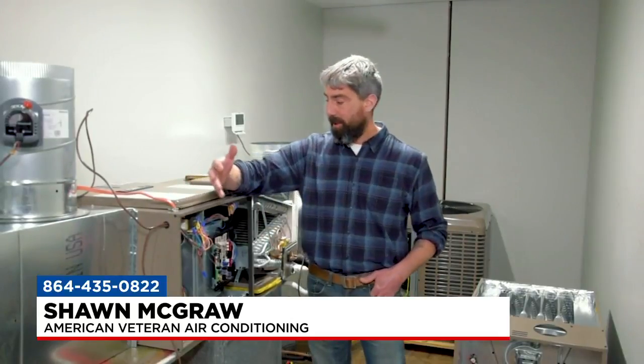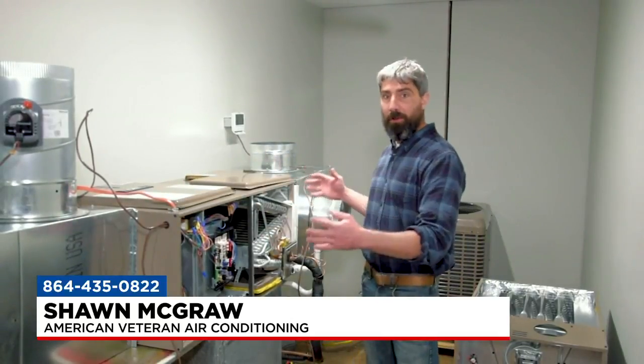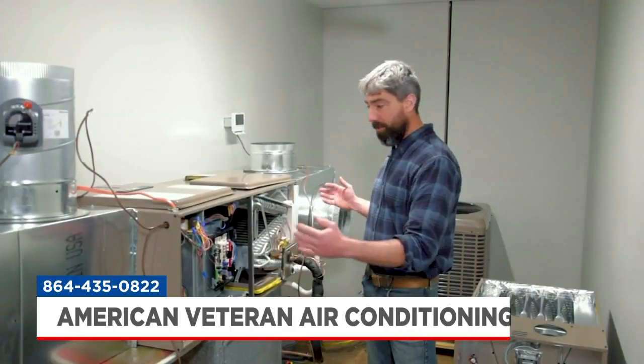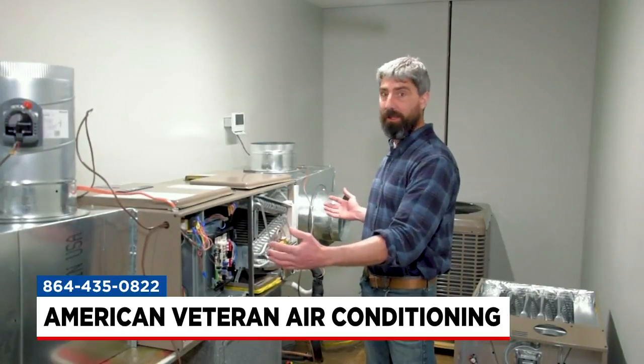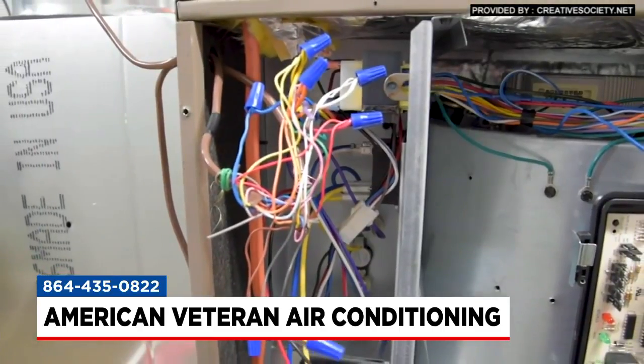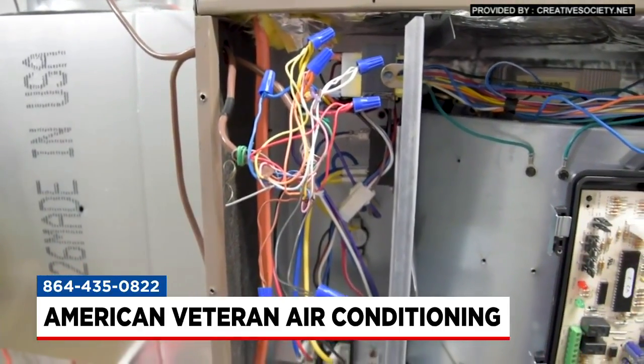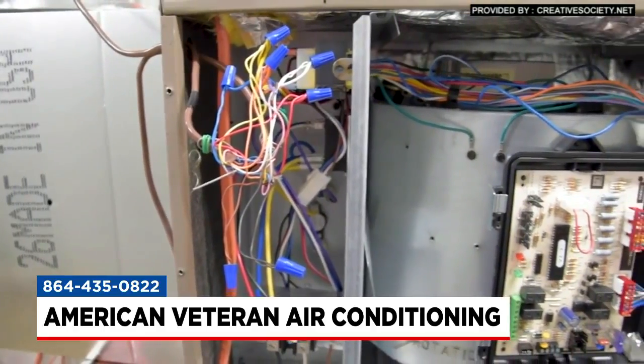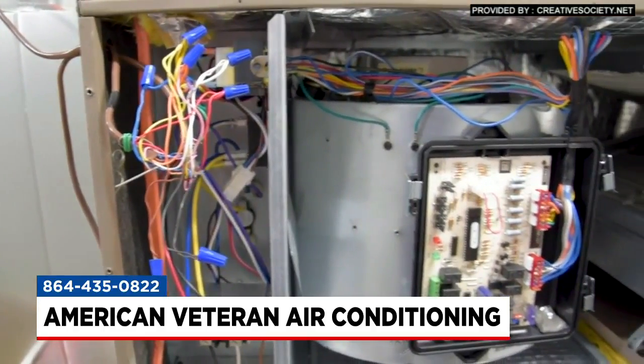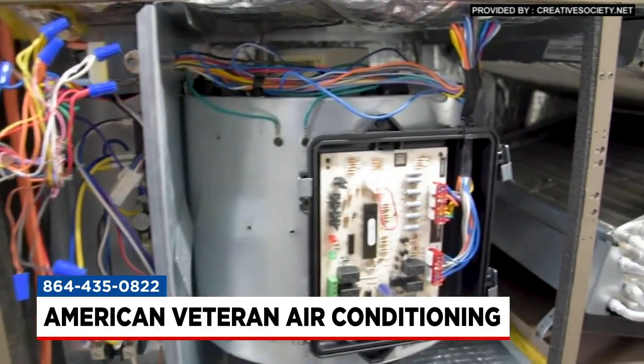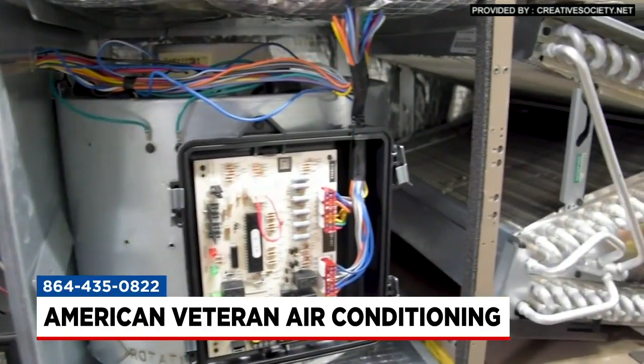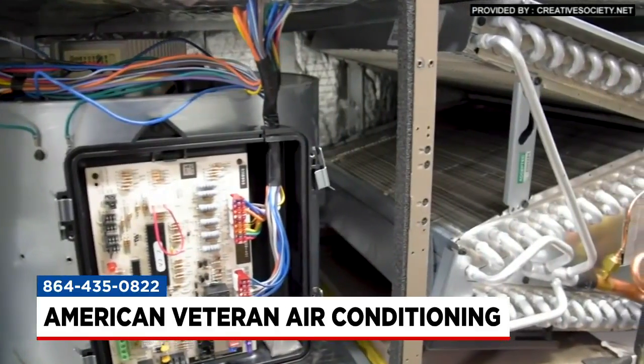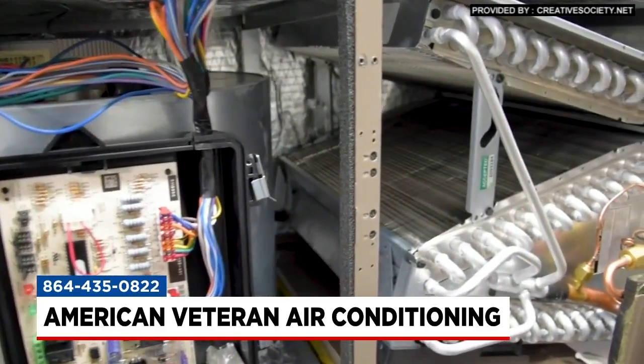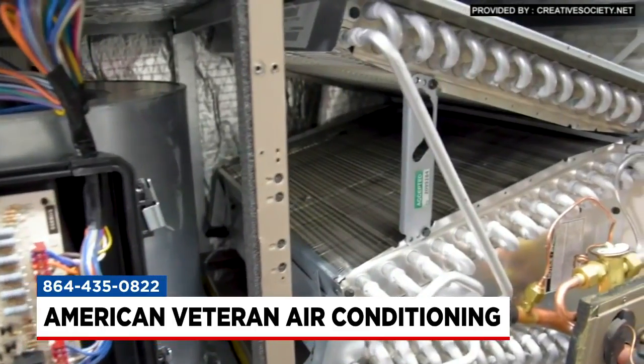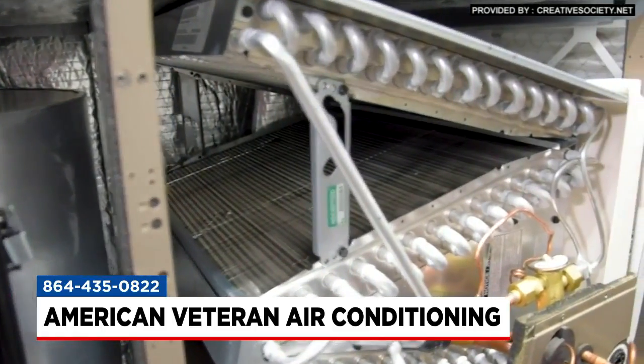So for a heat pump, we're going to do an overall inspection on the system, make sure it's operating properly right out of the gate. First thing we'll generally check is the airflow, making sure that it's getting the right amount of airflow going across it. So we'll start out on the inside, make sure everything's running right, make sure your coils are cleaned off well, that it's not trapping any dirt, the fan's putting out the proper blower speed that it's supposed to, creating the right CFM, check static pressures, make sure everything's good there. Then we'll move to the outside, make sure everything's working right there. Until we have the airflow set up, I can't really check the outside unit.